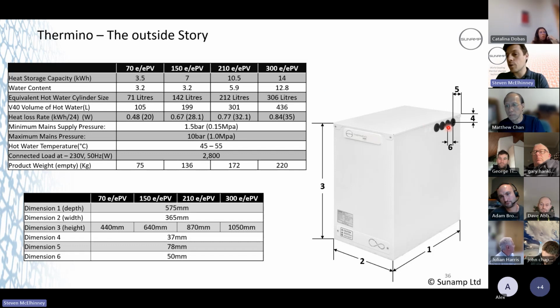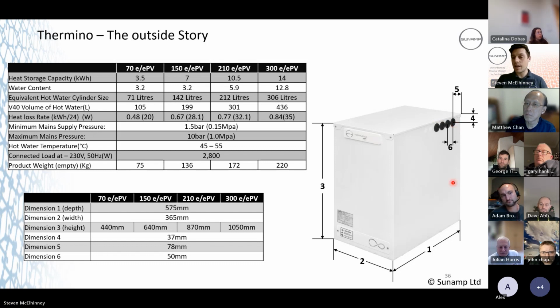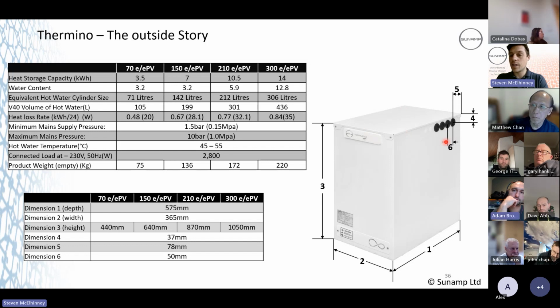Clearances to the side, if you've got your pipes and your cables coming out the right here, you need 150mm. So obviously you'd have 150mm, and then there's not enough space there to fit your TMV, but that's as a sort of minimal requirement. All other sides you would have 10mm, and 10mm back and left if you had a right hand side exit entry. We always need about 150 on the front.